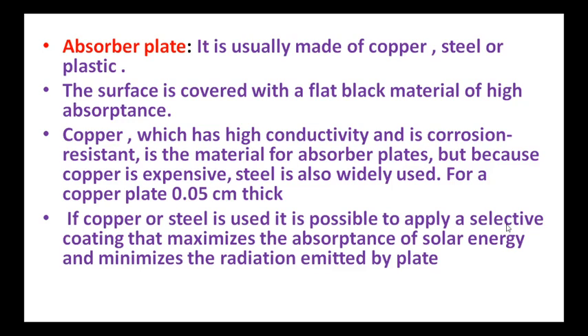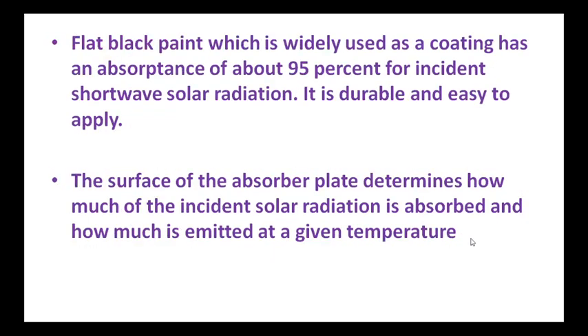The absorber plate uses flat black paint, which is widely used as a coating and has an absorptance of about 95% for incident shortwave solar radiation. It is durable and easy to apply. The coating is stable and does not require excessive maintenance.